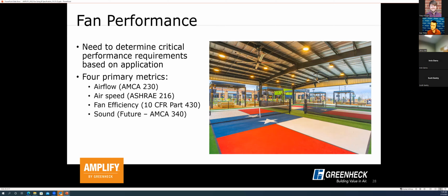HVLS fans being a little bit newer to the industry, there haven't historically been a lot of industry standards or regulations that could be used for defining some of these performance criteria. But over the last several years, that has started to change, and we're starting to see more and more standards be developed. So for airflow, there is an AMCA standard that's available. It's AMCA 230, and there is an AMCA certification procedure that is available for that standard as well to provide you with third-party certified and verified performance information on this type of equipment.